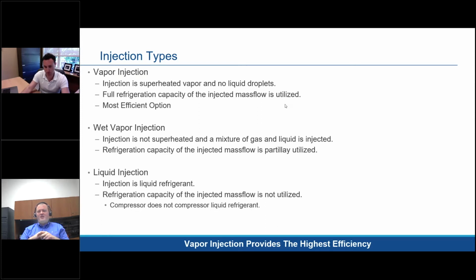You can get anywhere from 10 to 25% efficiency increase by going with a vapor injection offering versus a non-injection compressor. Wet injection is a mixture of gas and liquid going to the compressor. That's typically used for more extreme high compression ratio conditions, so low evap temperatures, which correlates with very low ambient temperatures, and high condensing temperatures, which typically correlates with higher supply air, or more typically higher supply water temperatures at that point.